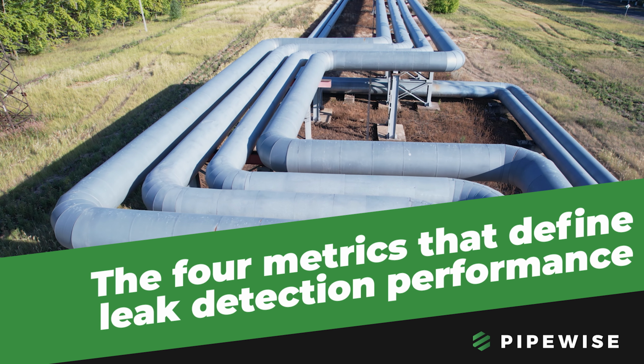So if you're talking about leak detection fundamentals, really what it comes down to is a form of anomaly detection. We've got a line balance across a pipeline and we're trying to identify when there's a deviation in that line. Is that due to a leak or is it because of something else? It's easy to look at the flow coming into the pipeline and the flow coming out of the pipeline and see that there's an error there. But what's really difficult is understanding when that error actually means that there's a release of product somewhere in the middle, or is it because of any number of other factors that can screw up a line balance?